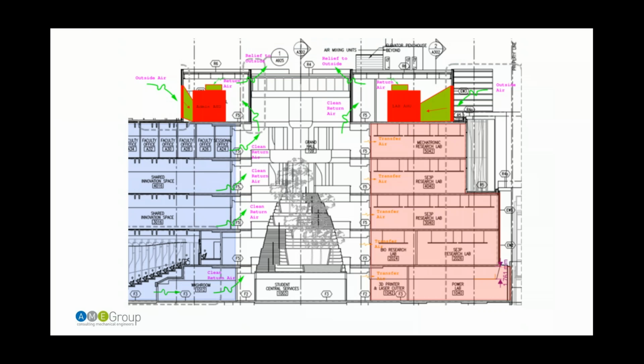And so just a little schematic here to show what it really entailed. From the left of the page, the clean return air from those office spaces and classroom spaces returns up into this big atrium, and either mixes back with the air handlers feeding those areas, or feeds back into our lab air handler on the right-hand side of the page. Any overpressurization that we might need or transfer air into those labs was again being used from the clean return air through the atrium and then transferring over into the lab spaces.